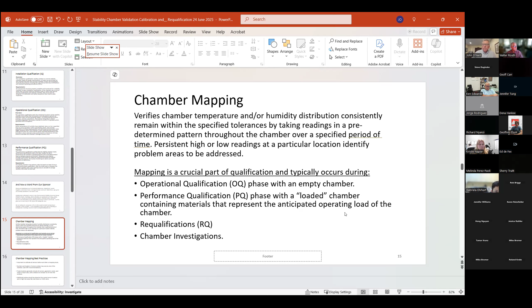Some best practices: it's important to calibrate all sensors before and after a mapping study. Number and location of sensor probes may vary by size of the chamber, and it's a good idea to check out the ISPE recommendations. The people who do this all the time have taken the time to develop a lot of information. The probe locations generally include all corners, geometric center, and center of each side with a distance of at least 10 centimeters from the surfaces. An additional probe should be placed at the control sensor location and in a high-risk area such as doors or HVAC vents.